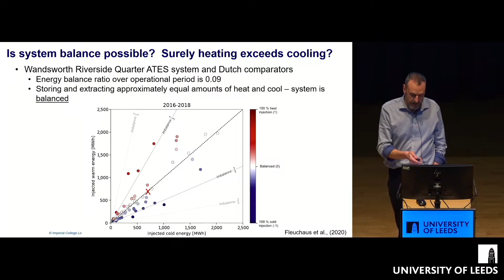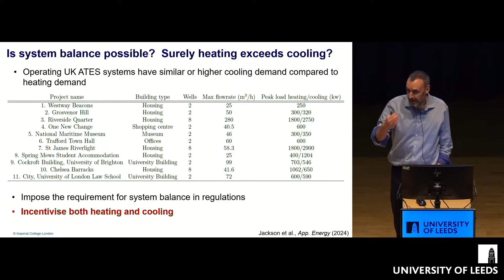What we're looking to do is develop systems that provide balanced heating and cooling. If you look across systems in the UK, they have pretty much equal heating and cooling demands, or in fact cooling demands that exceed heating demands. This is a list of different ATES systems showing heating and cooling loads, and you can see the cooling and heating peak loads are pretty similar, or cooling even exceeds heating. Historically, incentives for low carbon heating systems have really prioritized heating over cooling, penalizing cooling if it's offered, and they've also incentivized just the production of heat rather than the storage and reuse of heat. That's something we really need to change, to see these systems properly incentivized.